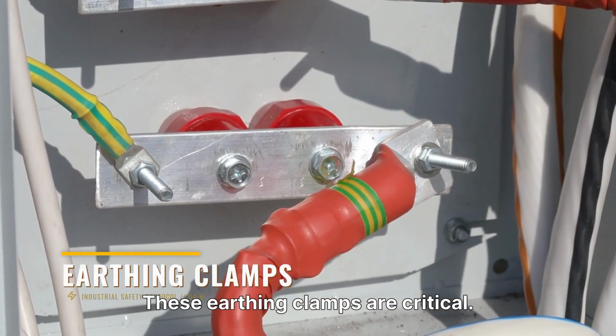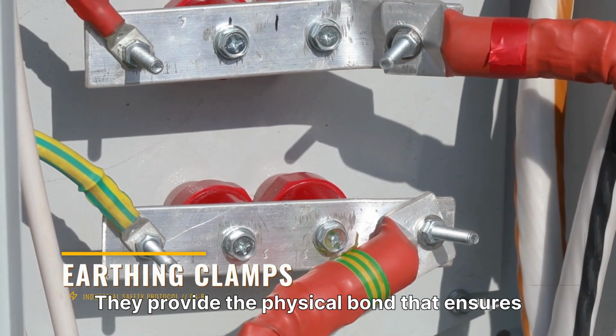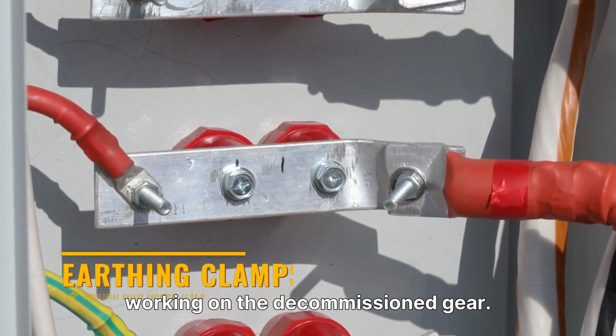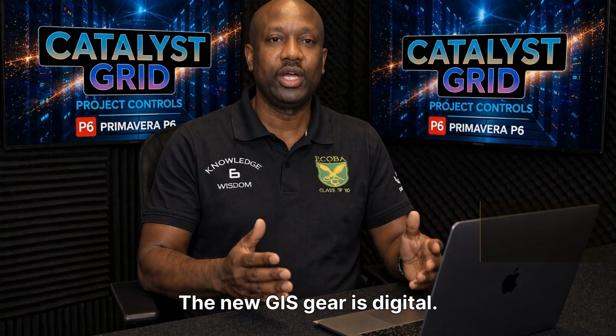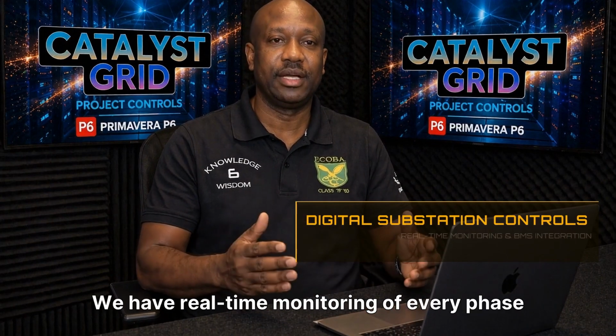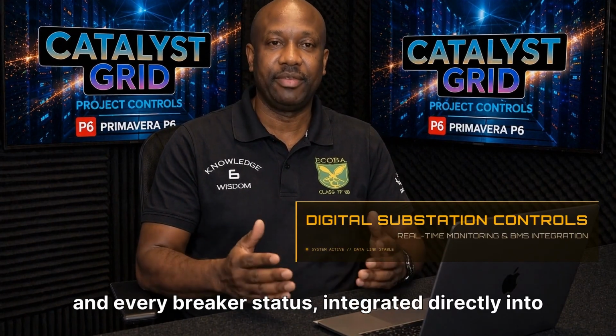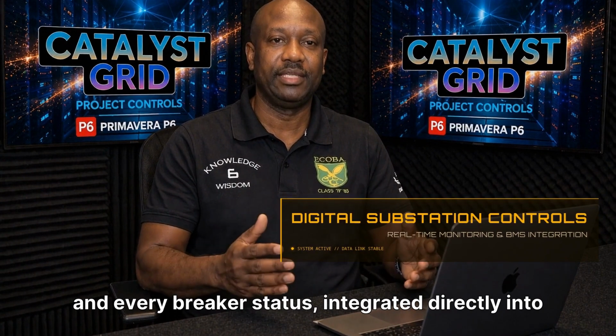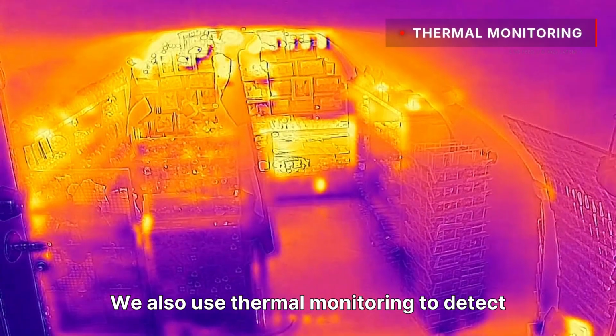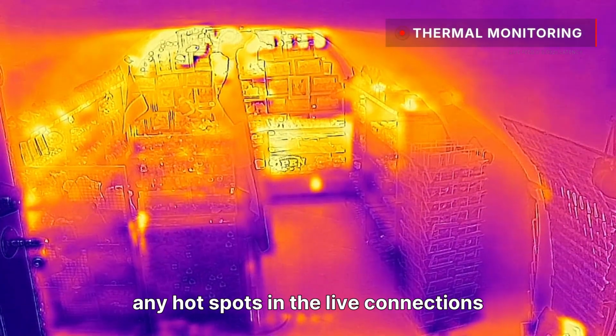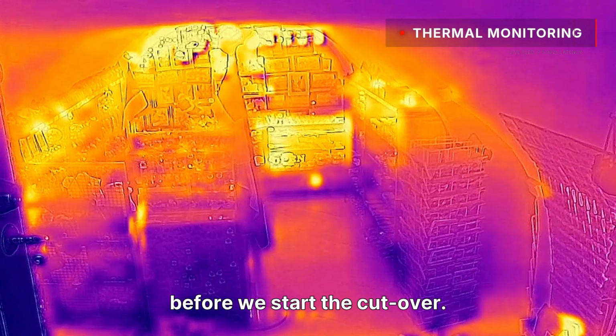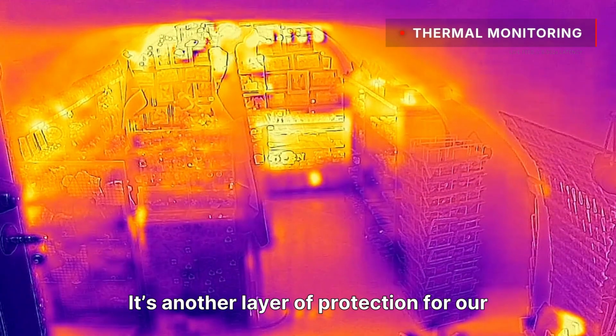These earthing clamps are critical. They provide the physical bond that ensures no voltage can return while we are working on the decommissioned gear. The new GIS gear is digital. We have real-time monitoring of every phase and every breaker status integrated directly into our BMS. We also use thermal monitoring to detect any hotspots in the live connections before we start the cutover. It's another layer of protection for our uptime.